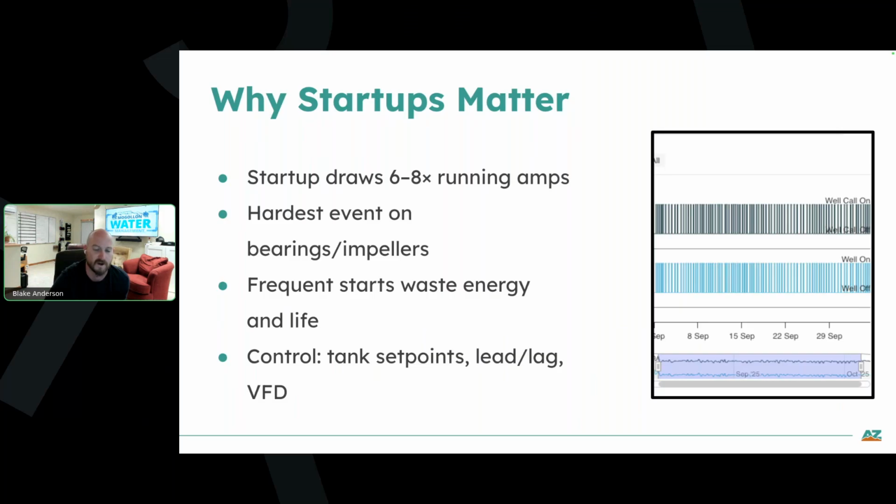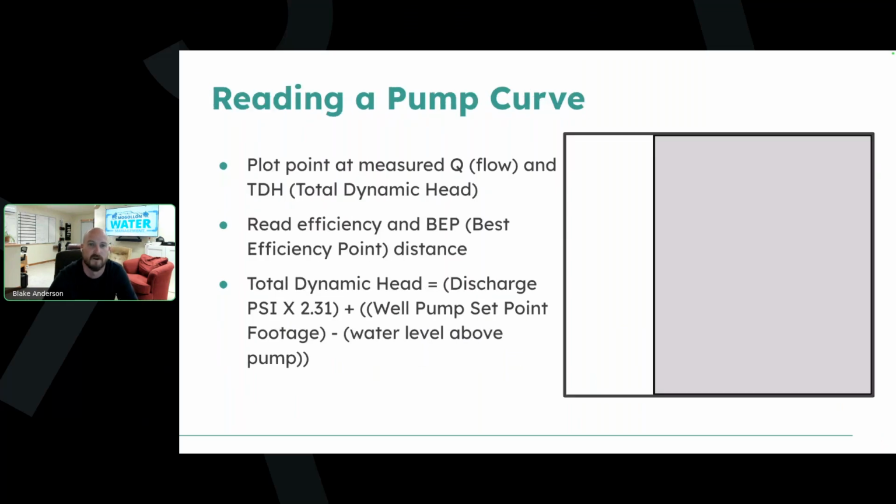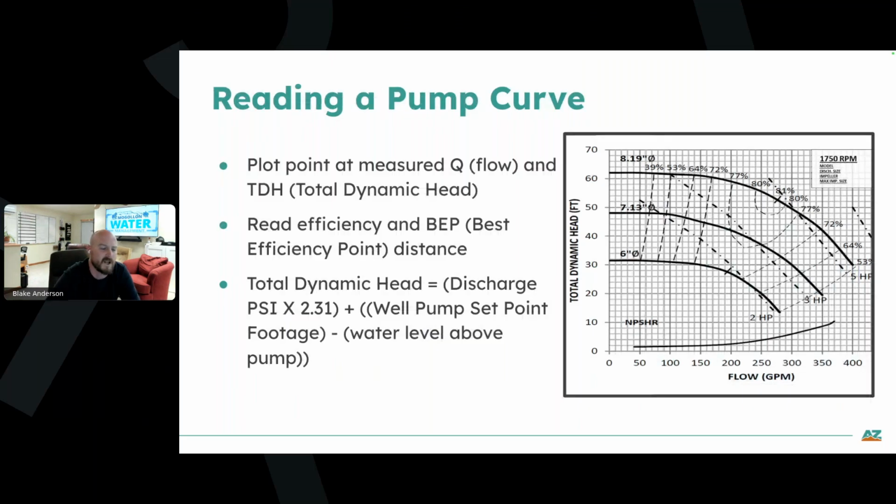So you can set wider tank dead bands. You can set it up to run your wells in a lead-lag setting. You could even install vibration and temperature sensors now on boosters or turbine pumps that can monitor in real time what your motor health is. I'm sure a lot of people have seen pump curves over the years going through their operator certification. This is really key information, especially when you go to replace stuff or look at making improvements. It's also a good way just to keep an eye on the health of your assets.